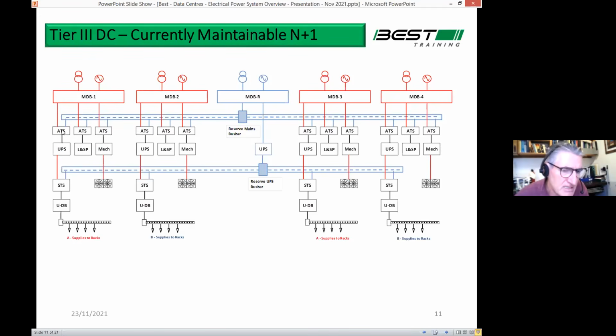Now you'll see each of those 3 loads is fed through the ATS that I referred to. ATS just stands for automatic transfer switch, and an automatic transfer switch just allows you to transfer the power from one source of power to another. Now, in this case, the red is the primary power coming off the main board. Okay, so you can see the next system has a red board as well. And the blue is the reserve. So the blue comes off the reserve system here.